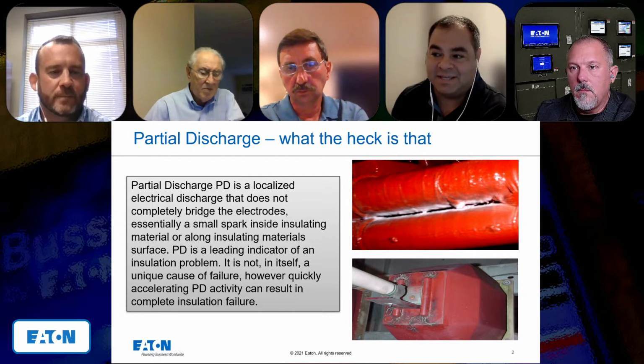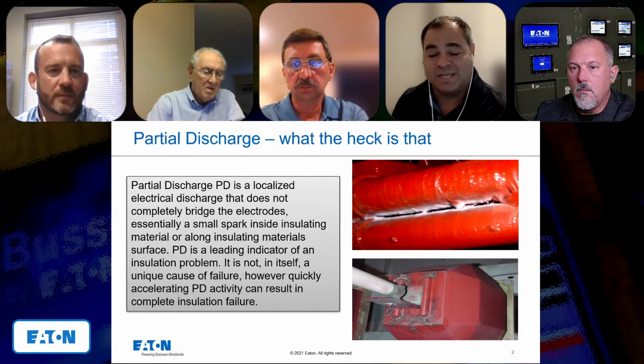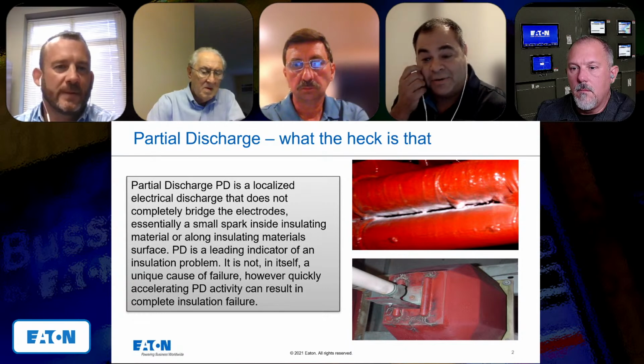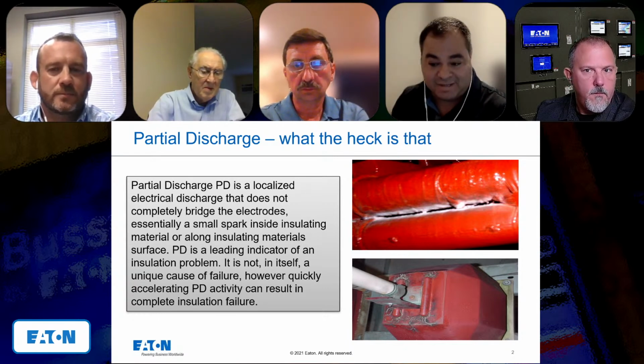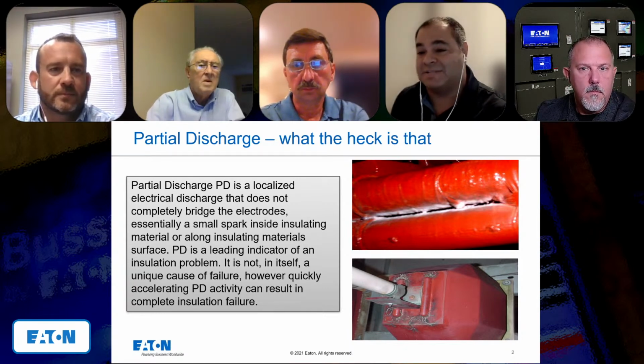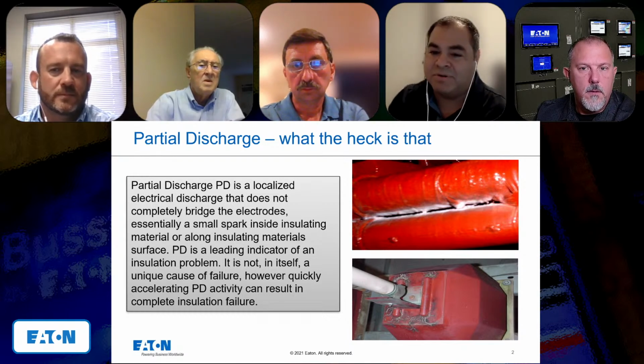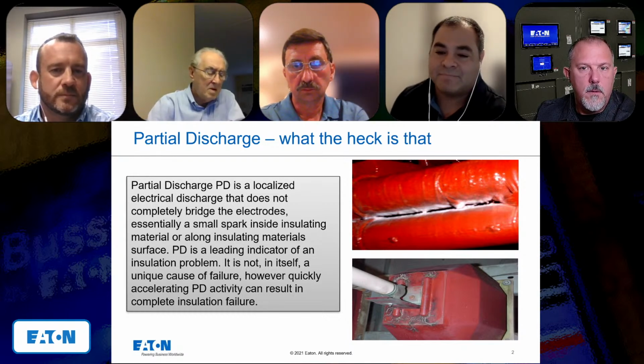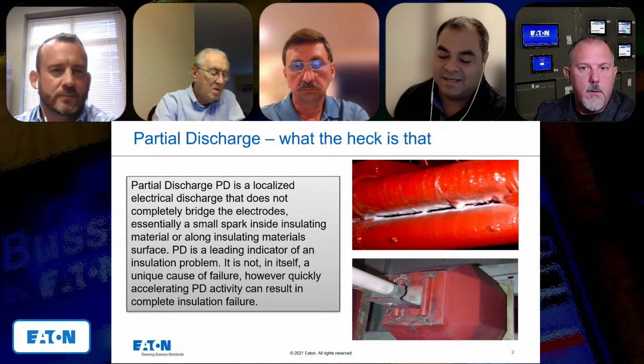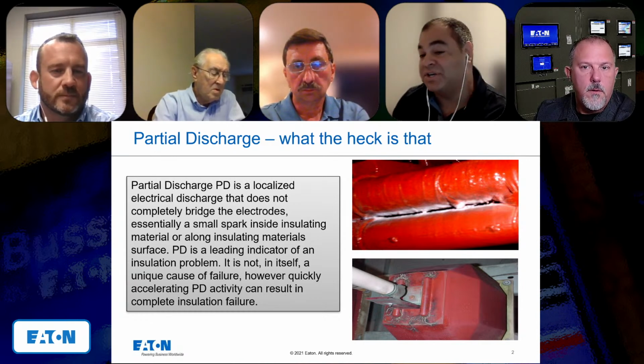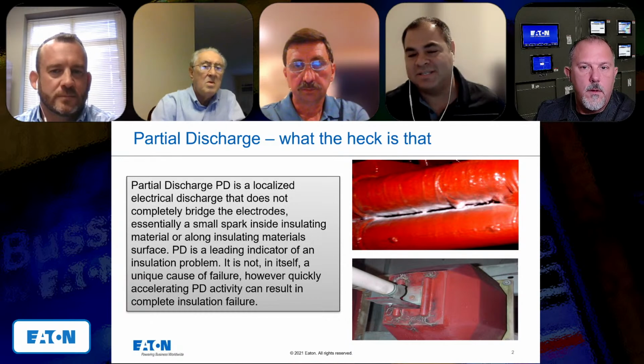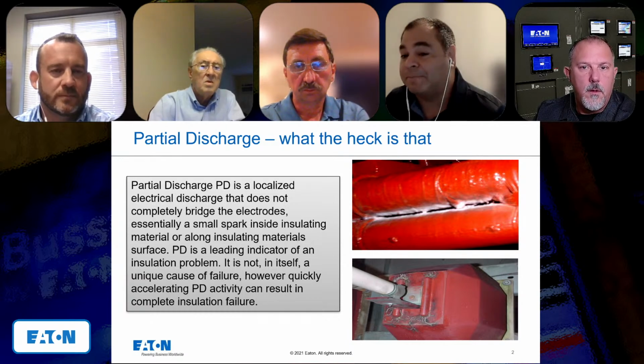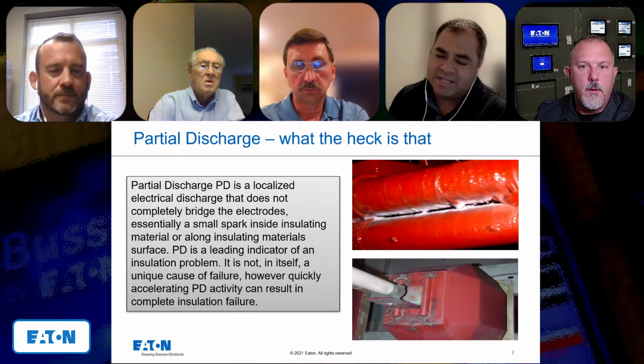The important thing is to follow a trend and see if the trend changes or something affects the motor, and then you kick off an inspection. This PD is typical for a motor, and the important thing is to follow the trend over the years. So as mentioned, this is not a one-day-to-another issue - it has a different history.